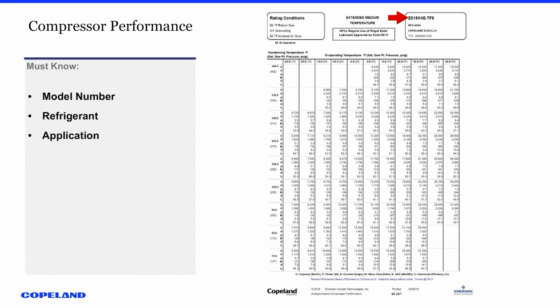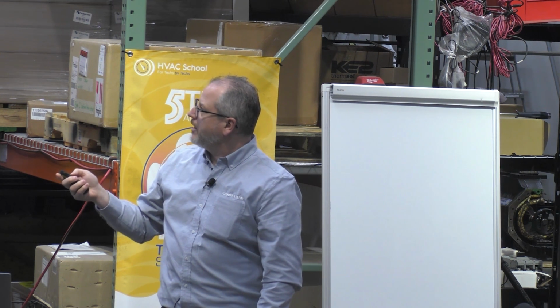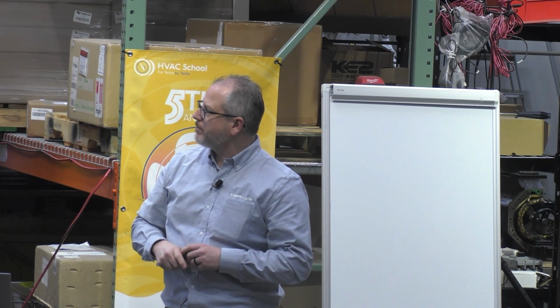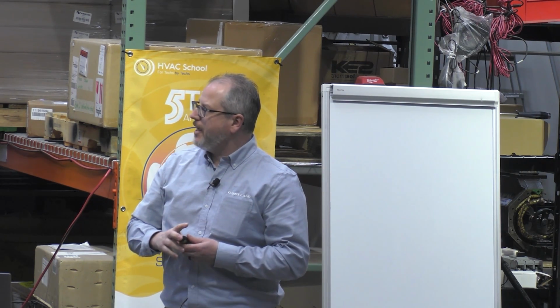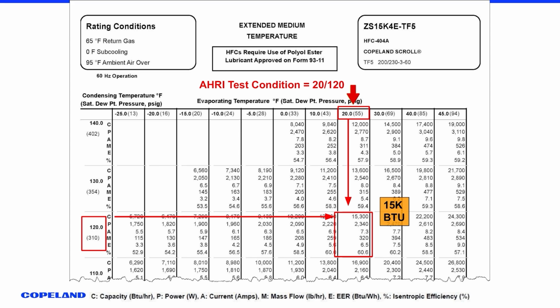This example, as you guys probably can't read that, is a ZS15 and then K. K is the multiplier, and 15 is the capacity. So as an example, I'm going to blow this up a little bit. So using AHRI guidelines for what they test medium temp units for, at 20 degree evaporator temp and 120 degree condensing temp, we're going to see what the BTUs is of this compressor.